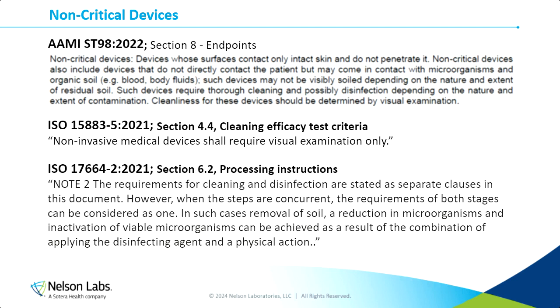So for example, if you have a non-critical device and you are using the same cleaner and same disinfectant for it, for example, a Super Sani-Cloth, that's a very common cleaner disinfectant you'll see at clinics and hospitals. It has that purple lid, the famous purple lid, I should say. If you're using that as your cleaner and disinfectant, and your device is non-critical, there is potential that you can perform a combination cleaning and disinfection study, because it's a one-step process where you're removing soil and killing microorganisms with these wipes. And we'll go into that a little bit further into the presentation.